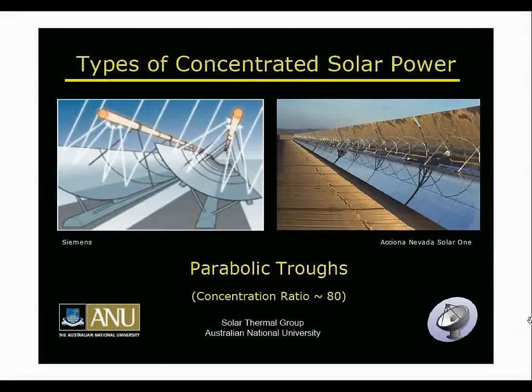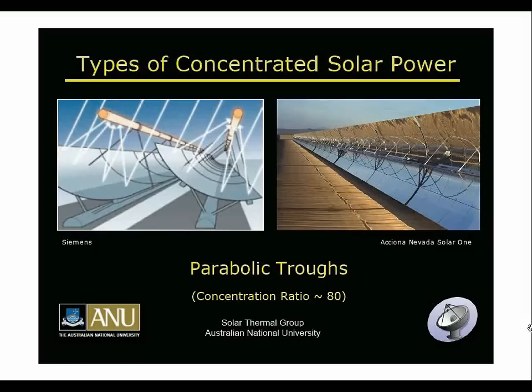There are four main types of reflectors in concentrating solar power. The first is the parabolic trough, used in the SEGS plants in California built in the 80s and 90s, the Acciona Nevada Solar One plant that started operating in 2007, and of course the Andasol plants. These have a concentration ratio of about 80 suns — meaning the ratio of sunlight falling on the mirror surface to the area where it's concentrated onto the receiver.